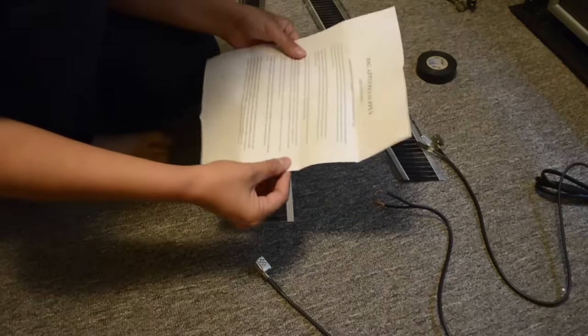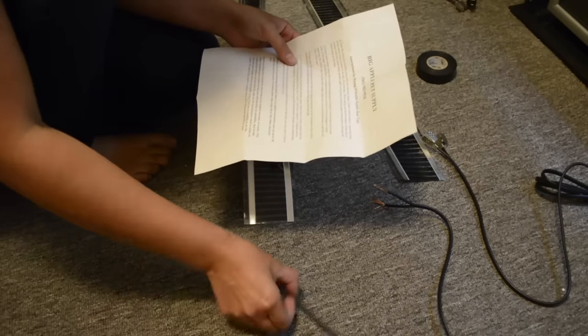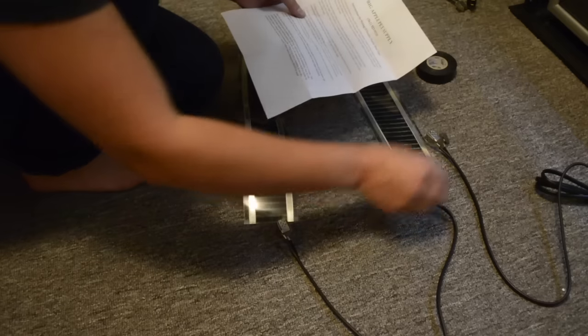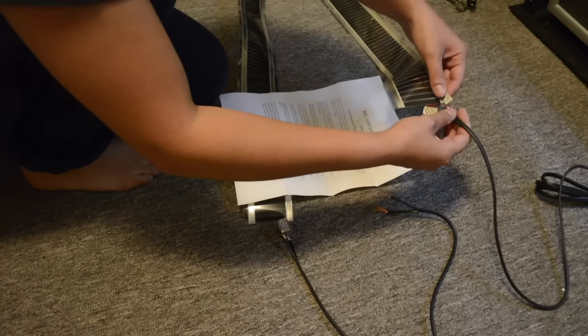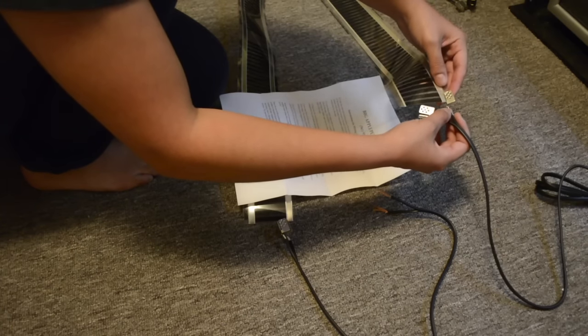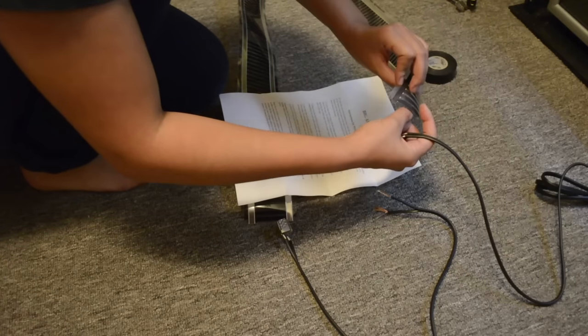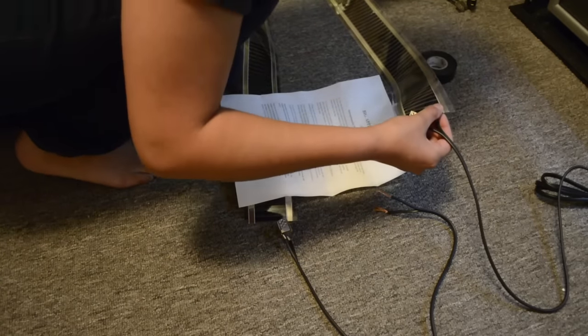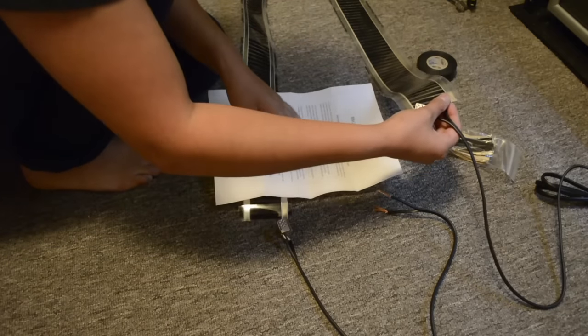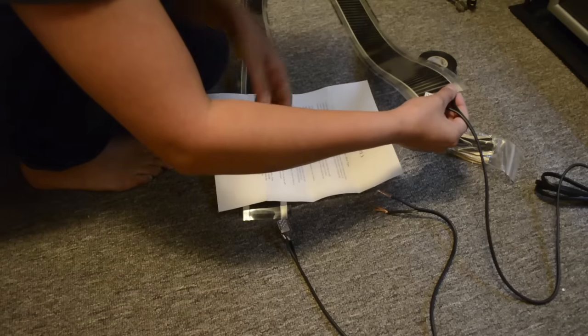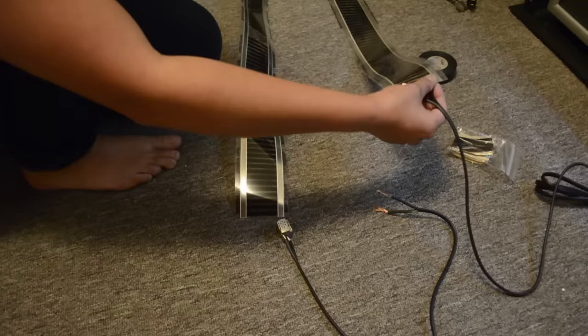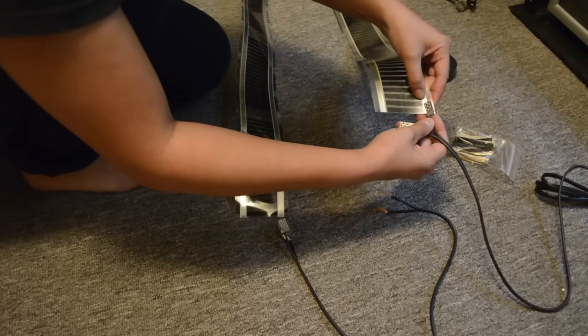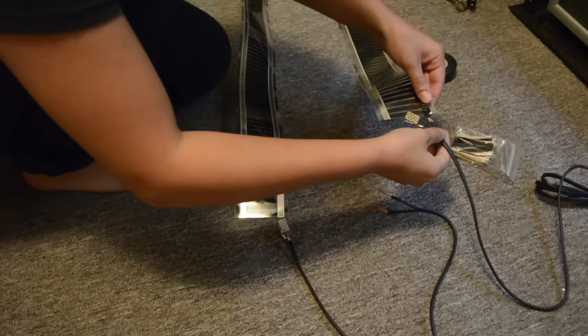So let's consult the instructions. Take the electrical hookup, the plug with twin wire and clamps. Attach a metal clamp to opposing sides of the metal strips at the end of the heat tape. While making sure that the copper clamps are in contact with the metal strips, squeeze tightly on the pliers so the copper clamp pierces through the metal strip on the tape. And of course they're talking about this part here. Cover each metal clamp with rubber insulating tape. Obviously do not have this plugged in. Make sure to use electrical tape to seal the cut side of the tape as well. Plug your cord from your heat tape into the thermostat. Blah, blah, blah. We'll look at that later.